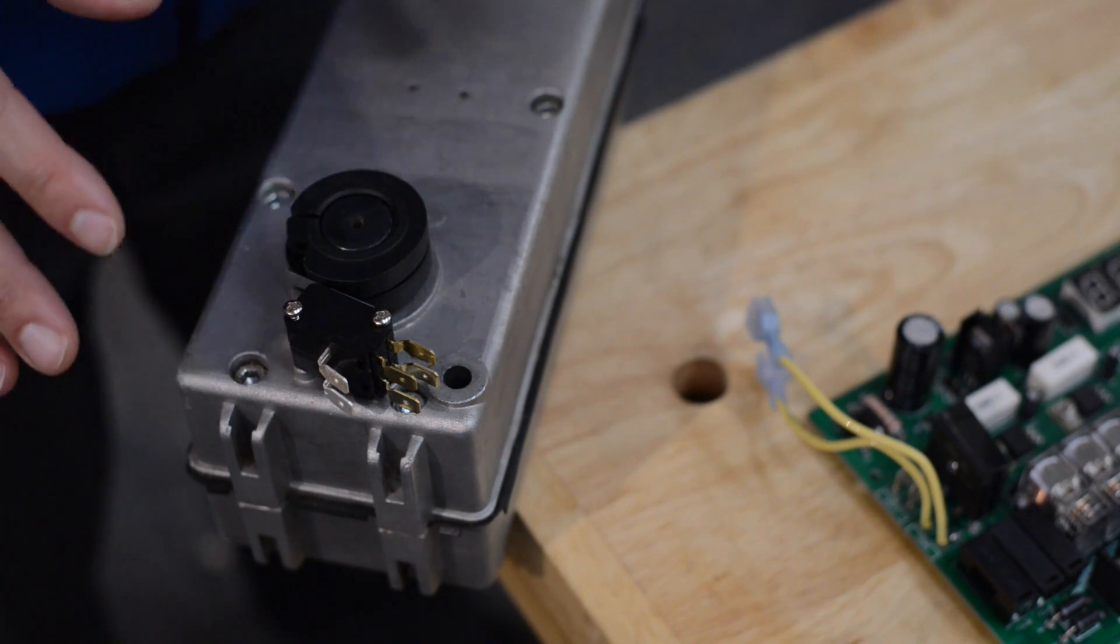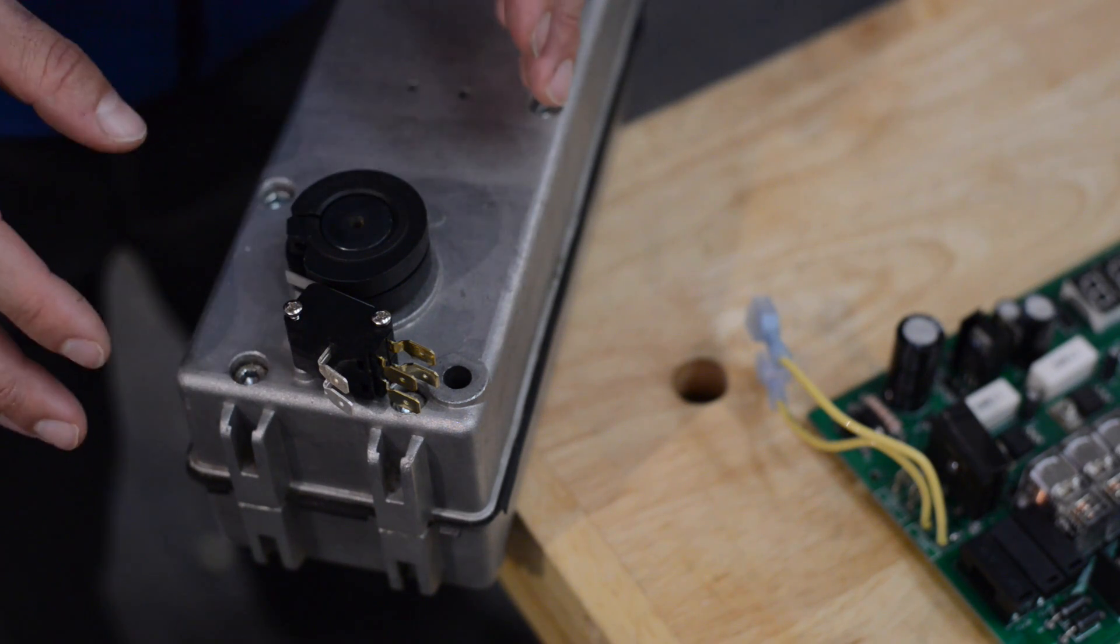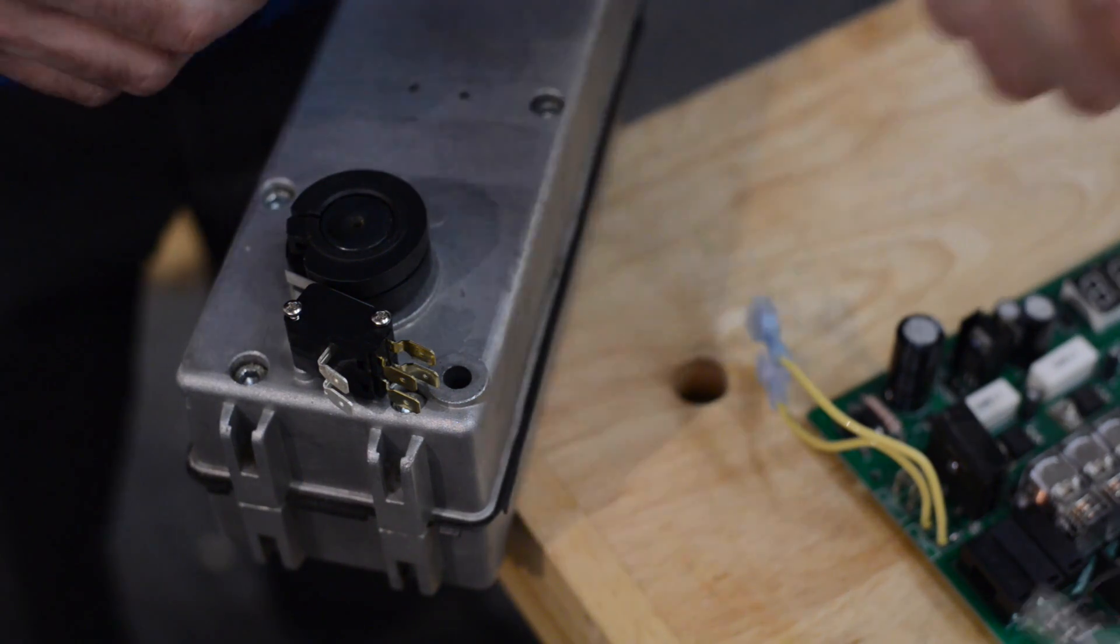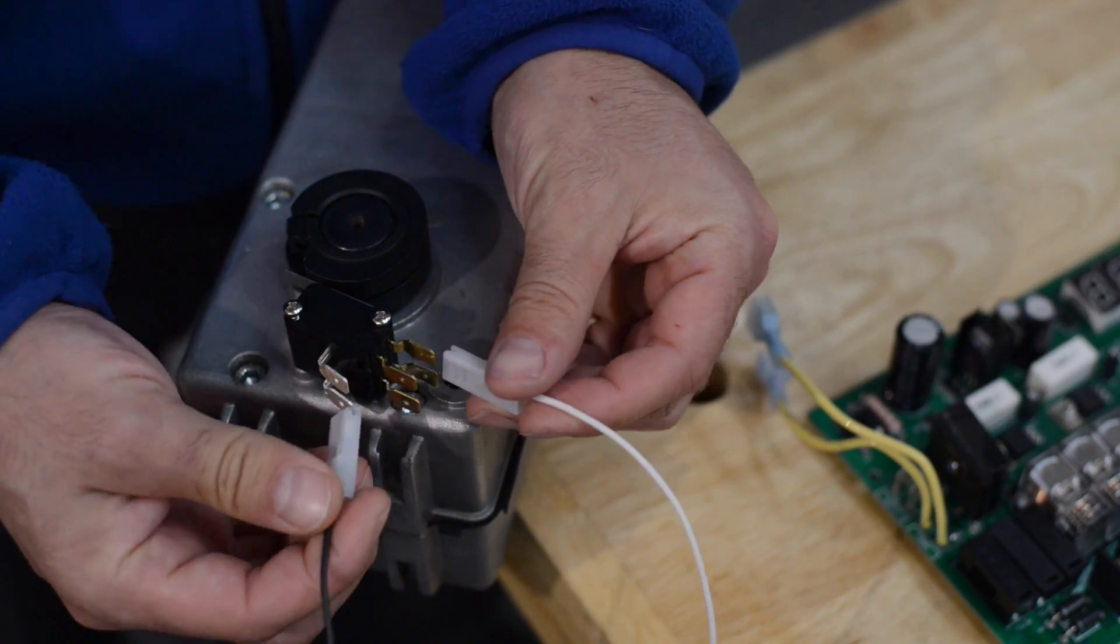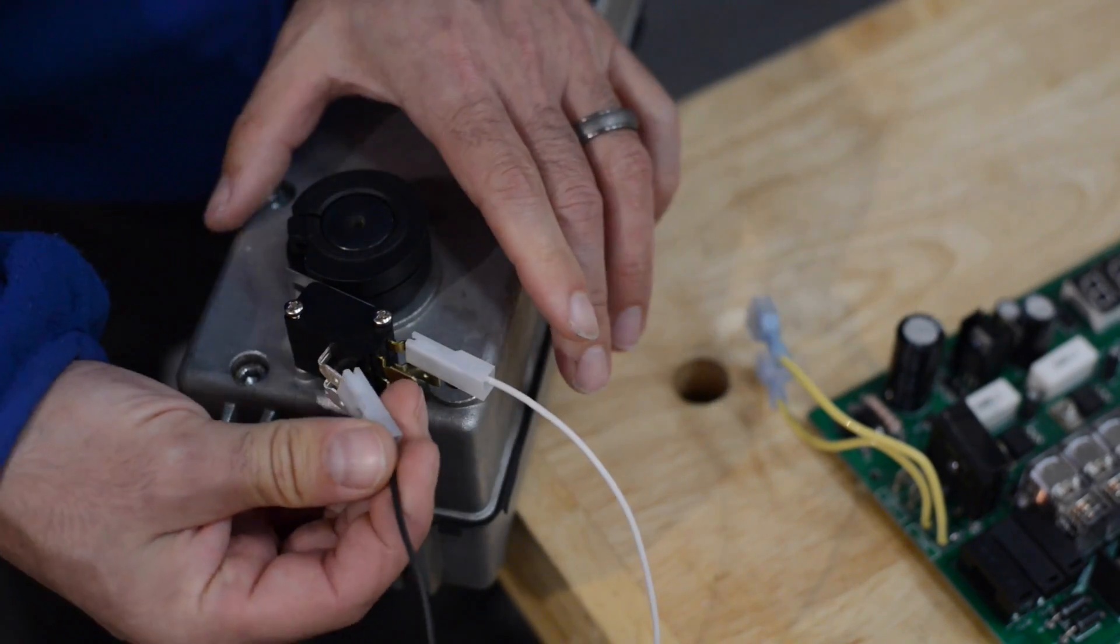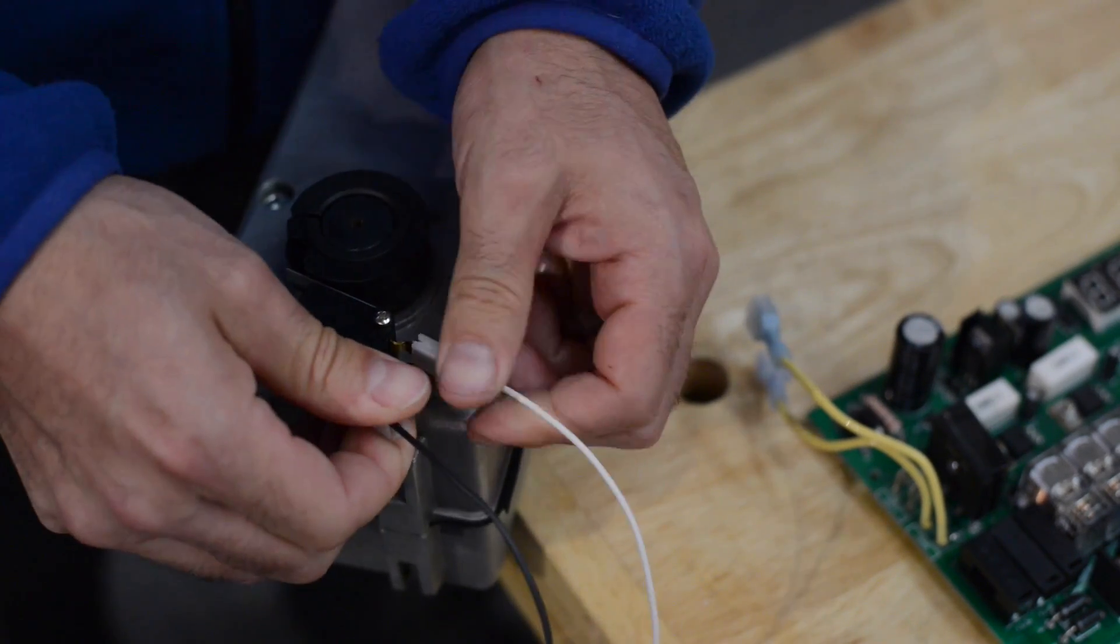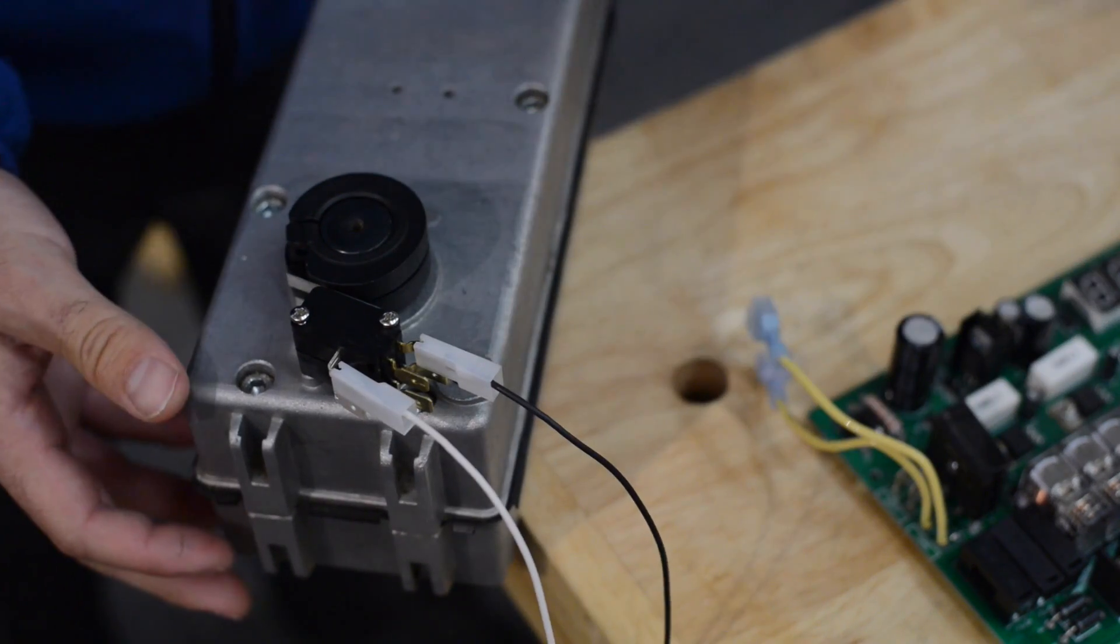Now that we have that solved now we can go on to identifying your common and your normally closed terminal on your limit switch. We get questions about which wire color because it comes with a black and a white. Well as you can see wire colors are not a reliable way to tell anything. I can put a black one here and a white one there. I can swap them, it doesn't really matter, it didn't change which one is my common and which one is my normally closed.